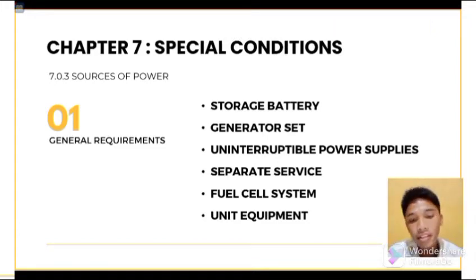The supply systems for emergency purposes in addition to the normal services to the building and meeting the general requirements of this section shall be one or more of the types of systems described in 7.0.3.1 letter A through 7.0.3.1 E. Unit equipment in accordance with 7.0.3.1 letter F shall satisfy the applicable requirements of this article, the 7.0.3 sources of power. In selecting an emergency source of power, consideration shall be given to the occupancy and the type of service to be rendered, whether of minimum duration as for evacuation of the theater, or longer duration as for supplying emergency power and lighting due to an indefinite period of current failure from trouble either inside or outside the building.